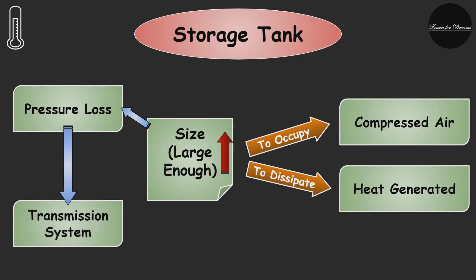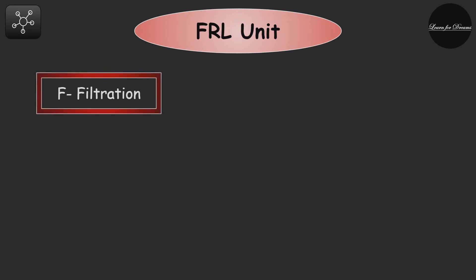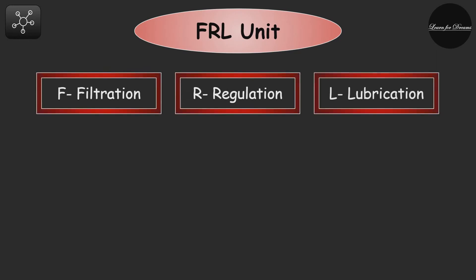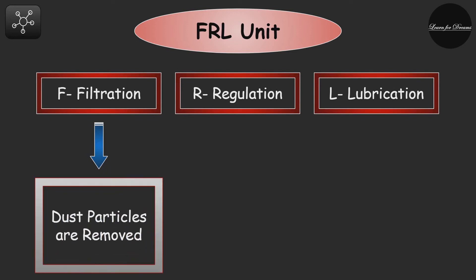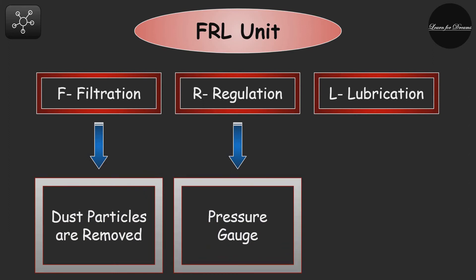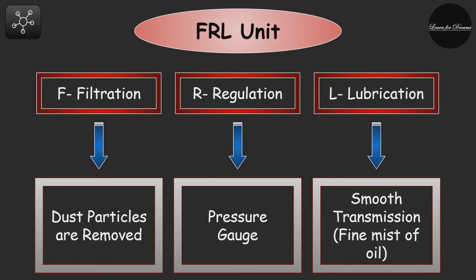Now let's see what is the FRL unit. F stands for filtration, R stands for regulation, and L stands for lubrication. The atmospheric air is contaminated, so it is filtered to remove dust particles to avoid their entry into the actuator or the transmission system. A regulator is used to regulate the pressure of the air, and the required pressure can be set through a pressure gauge. Lubrication is used so that the compressed air flows smoothly through the transmission system, where a fine mist of oil is created and mixed with the compressed air.